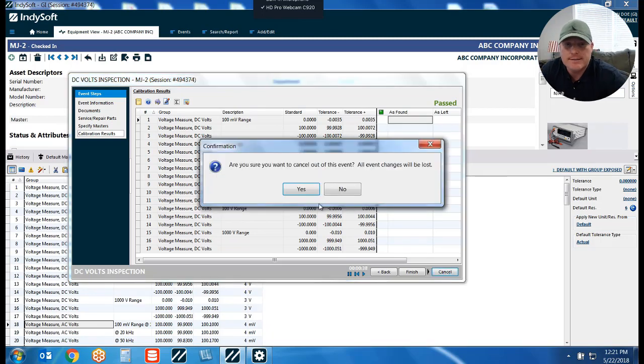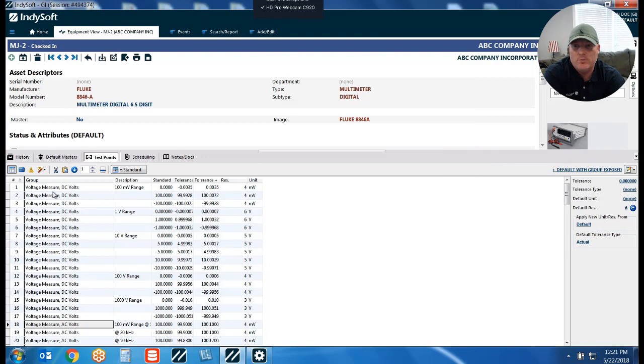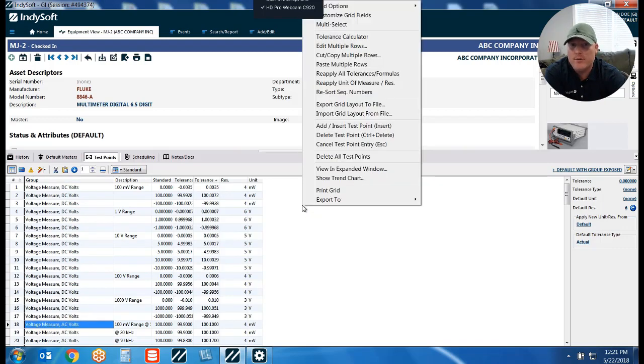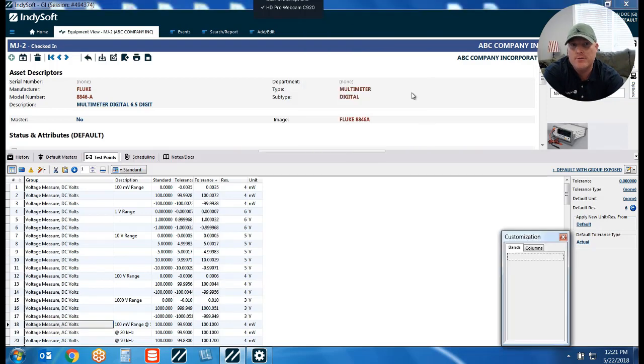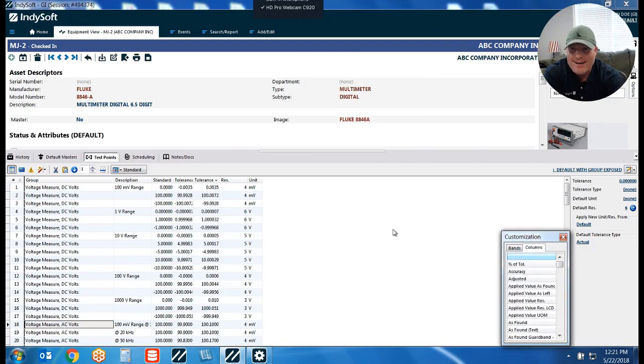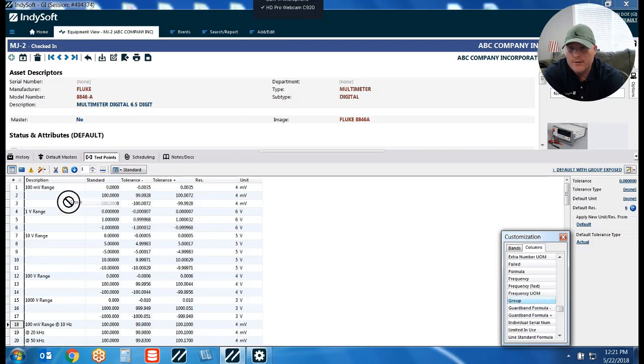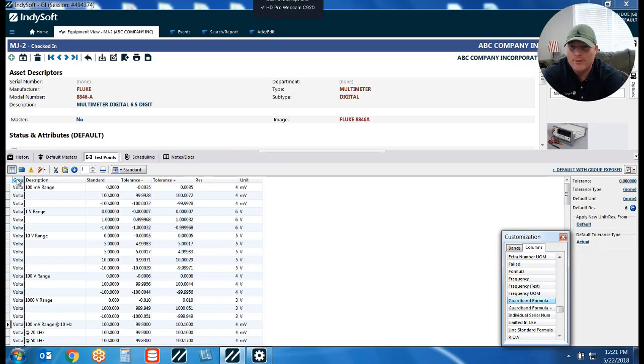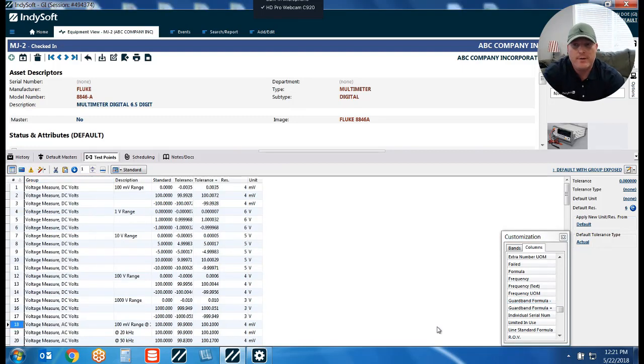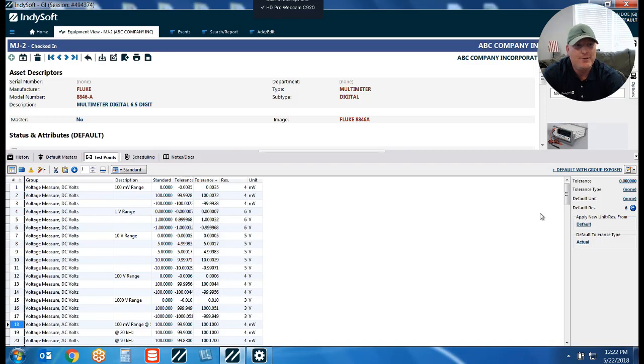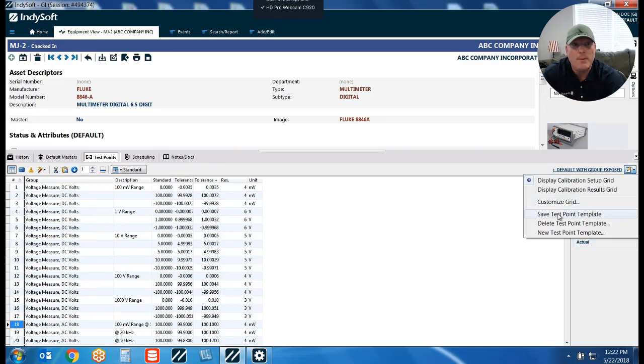Here's how we set that up. It involves two things. First, we have to make the group column visible in your test point grid. To do that, anywhere in your test point grid just right-click and you'll see an option called 'Customize Grid Fields' — choose that. You would drag and drop the group column into the visible area of the test point grid. Keep in mind if you ever modify a test point grid column structure, you will need to save that, otherwise next time you come back it will be gone again.